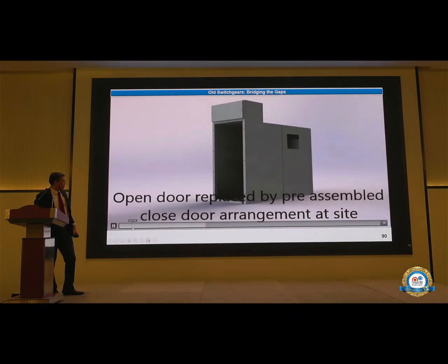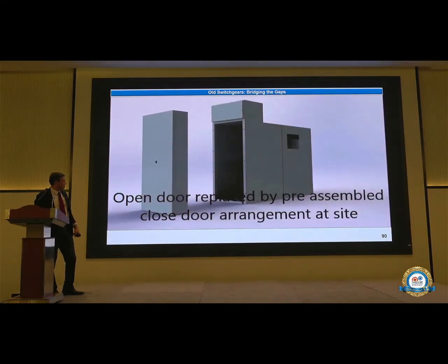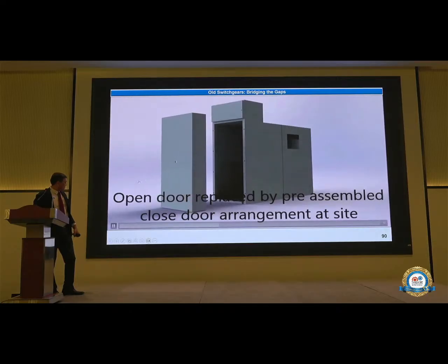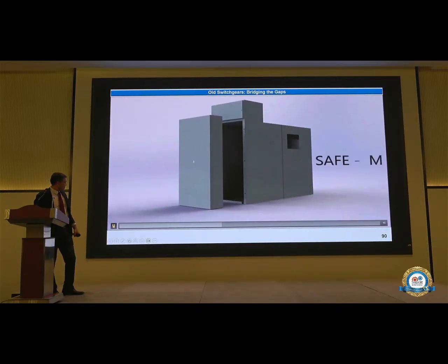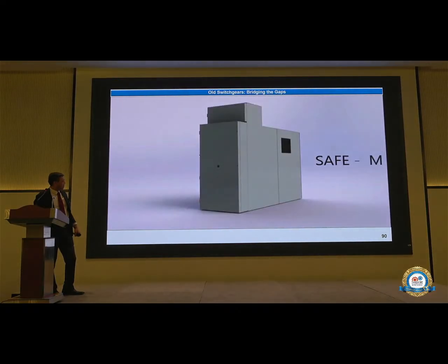It is possible to replace the open door with a pre-assembled closed door arrangement at site. It makes the switchgear safe, so we call it a safe module or safe end. This can be fitted to any existing switchgear with minimum changes.